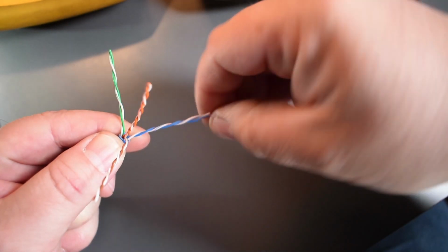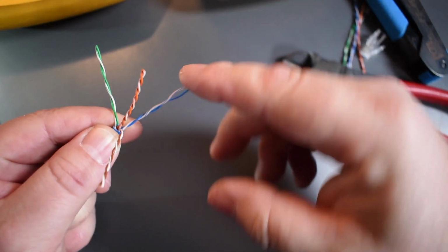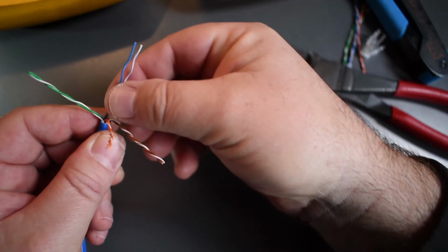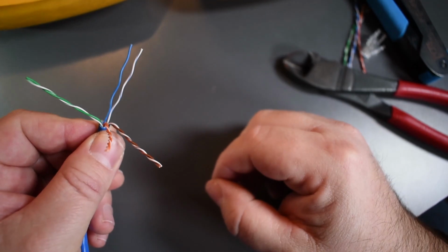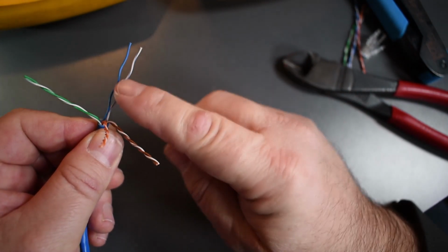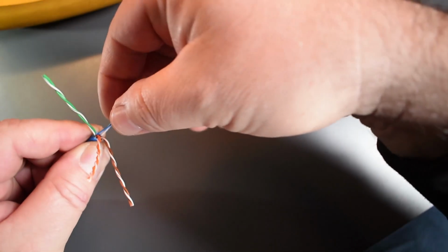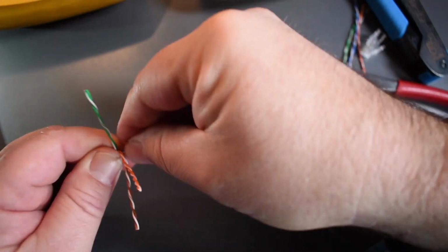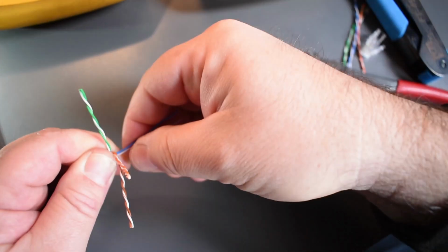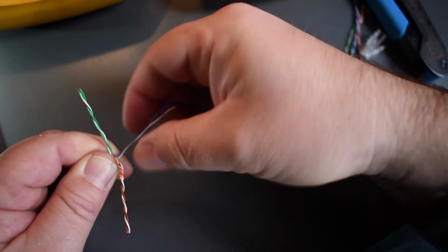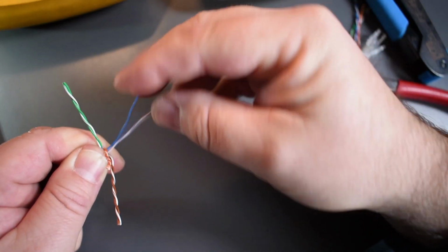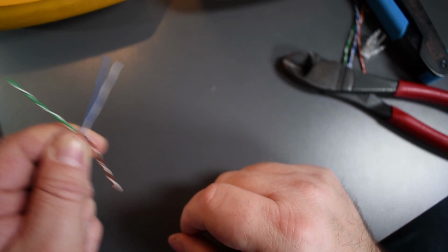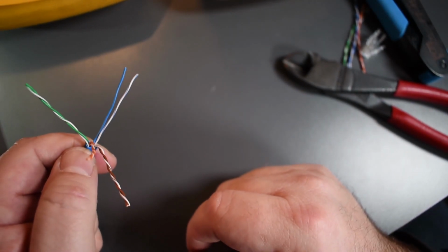So I'm just going to untwist the first pair, and remember all the stripes are going to the left except for the first pair, which is the blue pair. Now if I untwist those, you can see that there's a little bit of residue from the twist. The way we do this, you just squeeze the pair and just kind of shake it around as you're pulling outwards, and that gets rid of the twist residue. Just make sure that the pair doesn't reverse on you as far as polarity. So this is the first pair that is going to be inserted into the jack.